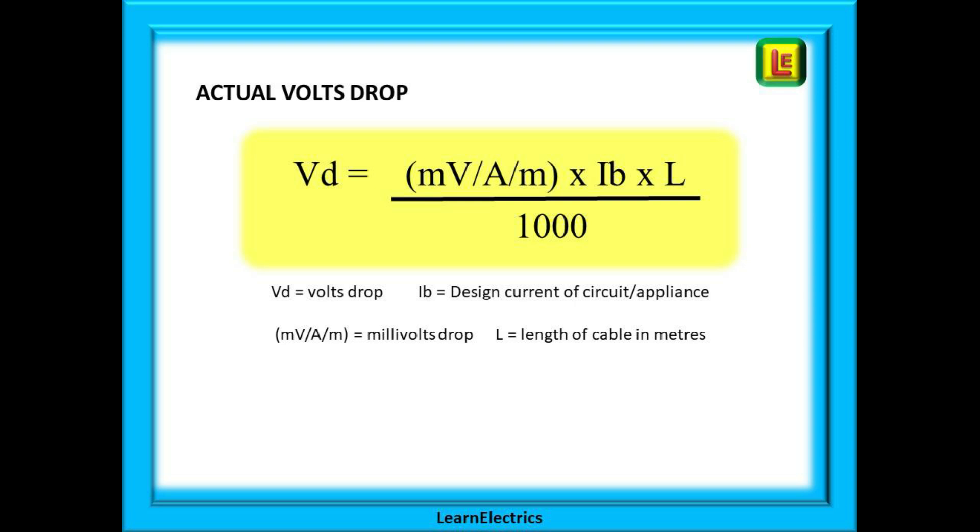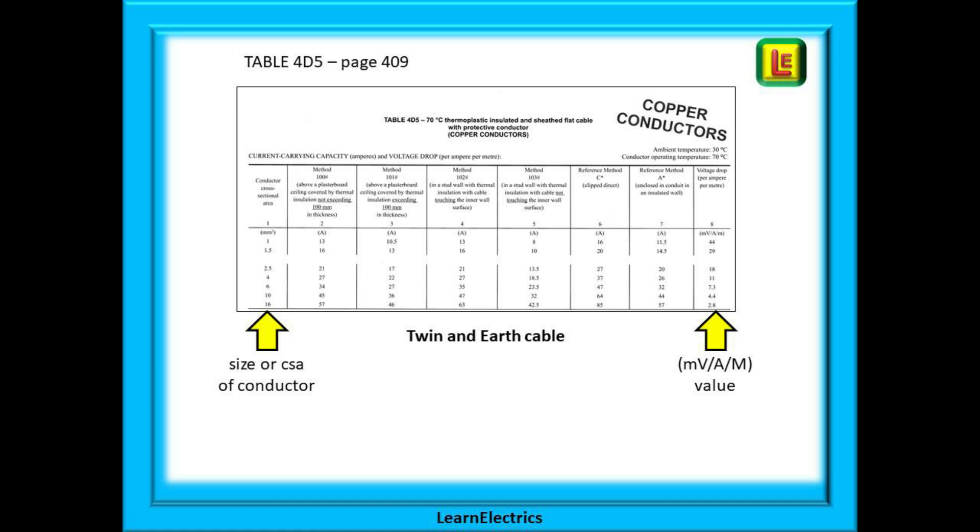Here we have the formula to use for calculating the actual voltage drop in a cable. It looks complicated, it isn't. Just below the yellow box we have listed the four terms that we use in the calculation and what they mean. And the number here, 1000, is there to convert millivolts back to ordinary volts so that we can make a direct comparison to the maximum permitted voltage drop from table 4AB earlier. Every cable has its own data page, and in this video we will focus just on twin and earth cable or flat cable as the book calls it.